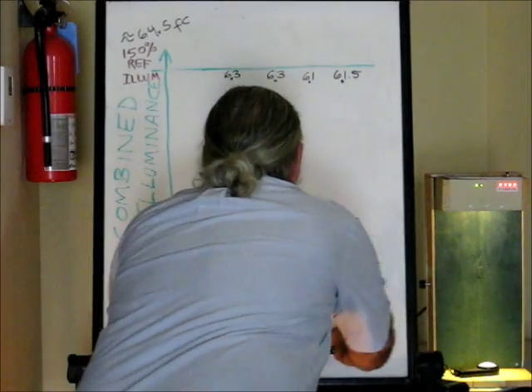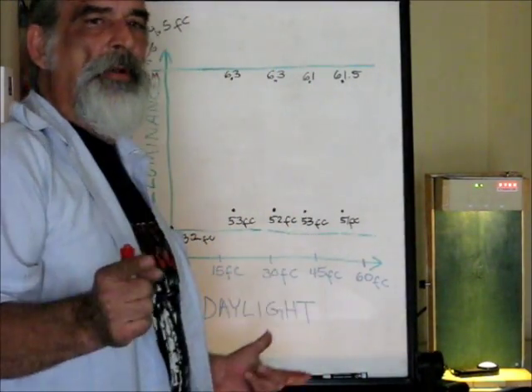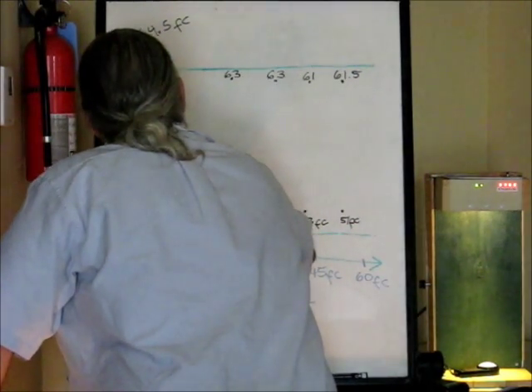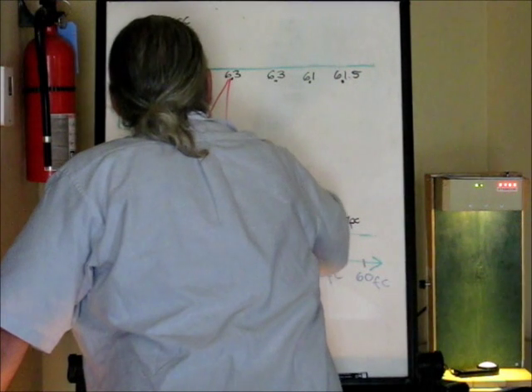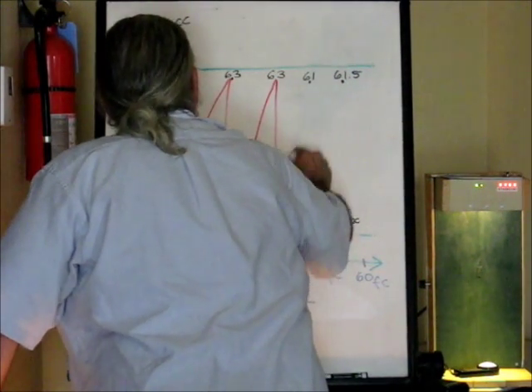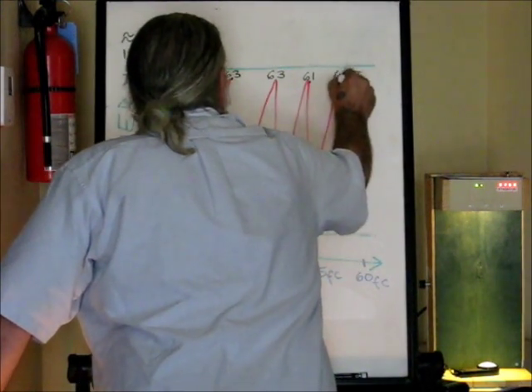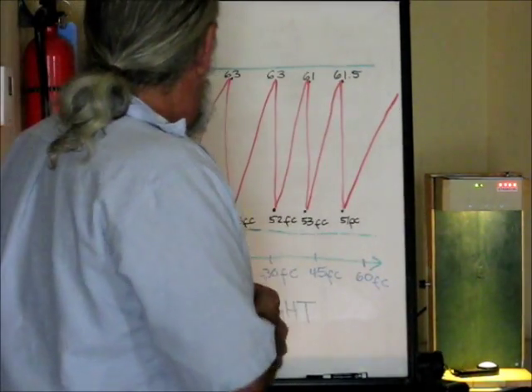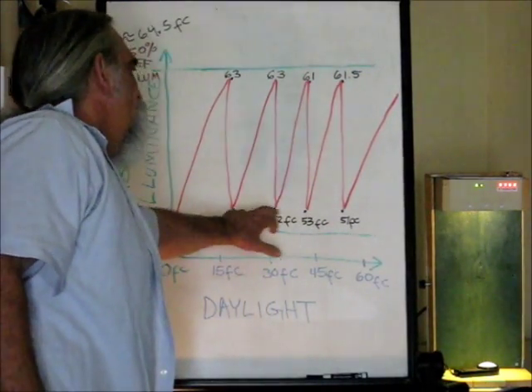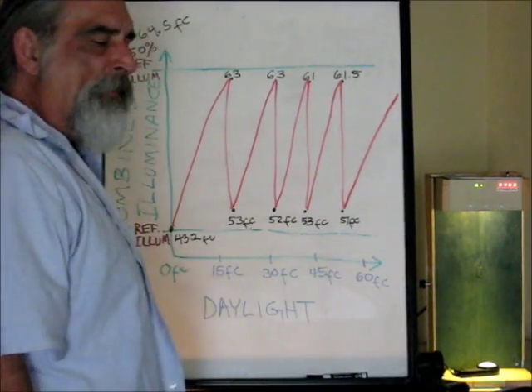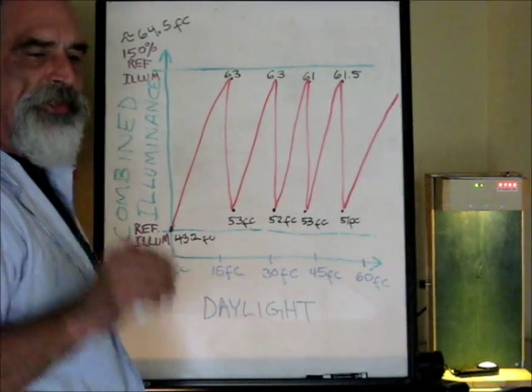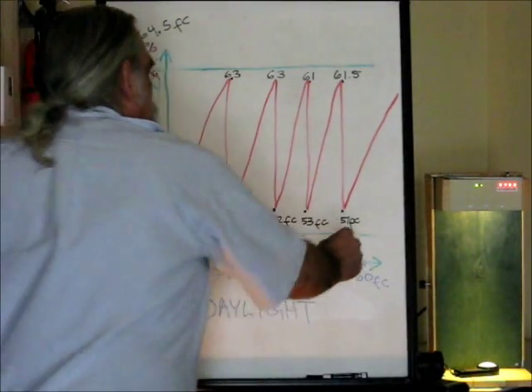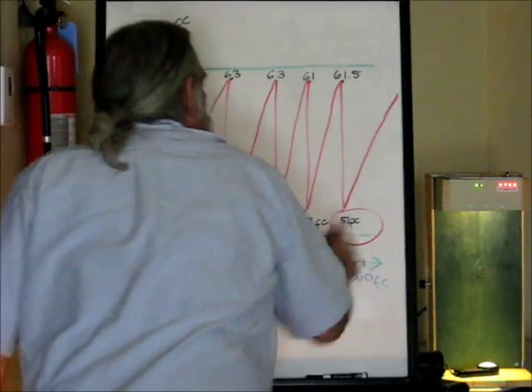Now, if I connect the dots, this is going to show me what a printout of an actual logging light meter would look like in this area. The sun comes in. First stage of light snaps off. Sun comes in. Second stage snaps off. Sun comes in. Third stage snaps off. Sun comes in. Fourth stage snaps off. And the rest of it is all going to be daylight. Here are our partial illumination, our partial daylight test points. If you have up to three stages, you test them all. If you have more than three stages, you pick three.